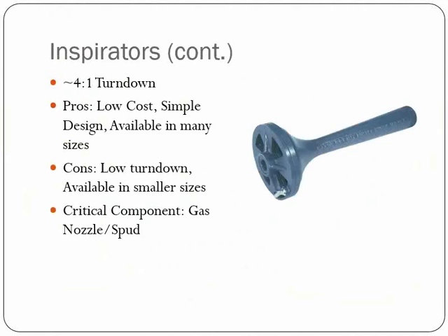The cons are low turn down. Actually, availability in smaller sizes should be one of the pros, and I have it listed there. But the main con with the inspirators is the lower turn down. So if we're looking to get increased control out of your system or being able to control over a wide range, the inspirators aren't really the best at providing that flexibility.